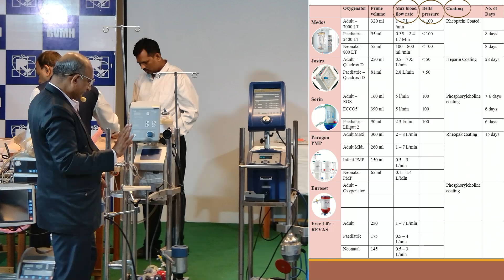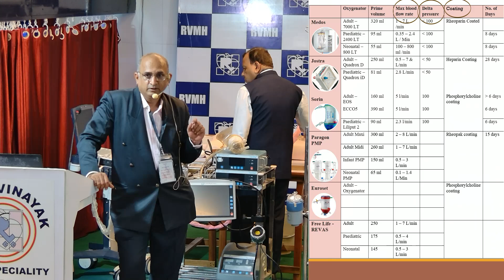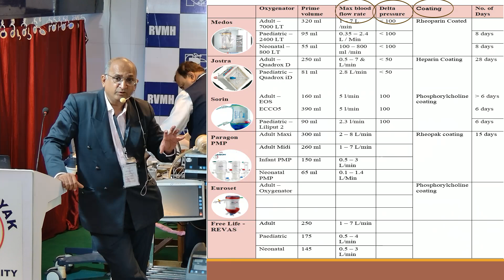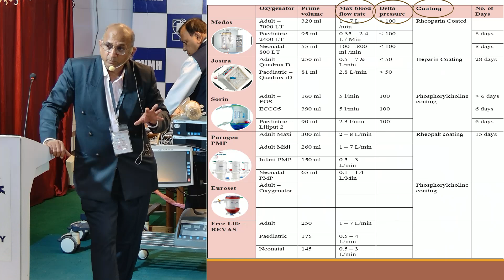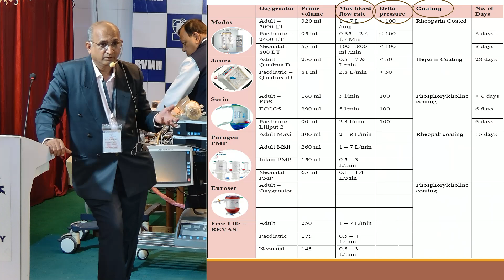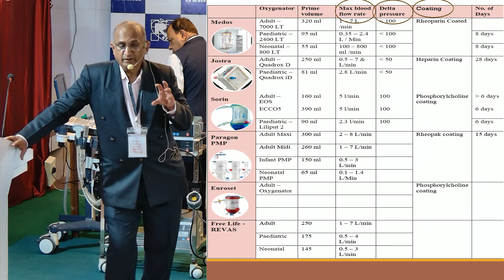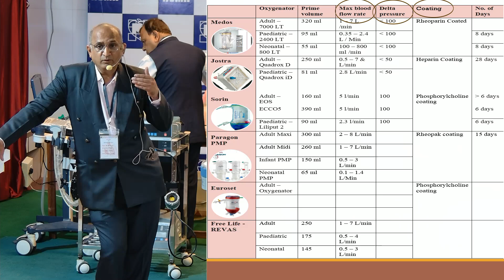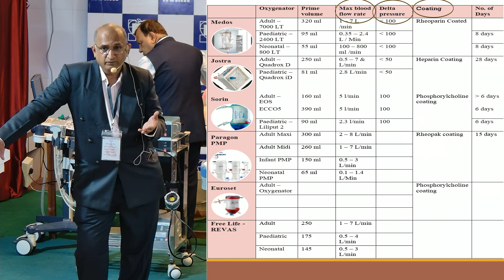Now for each oxygenator, what is important is the rated capacity. What is rated capacity? It means each oxygenator has a maximum capacity of oxygenating the blood. Some oxygenators have a capacity of 5 liters of blood, some 7 liters, some 2 liters, some 800 ml. So you should know the rated oxygenating capacity of each oxygenator. Why is this important? Because if you go above that flow, you won't be able to help in oxygenation, but at the same time you will create more resistance, and it will lead to hemolysis.